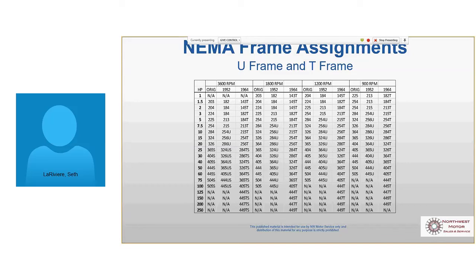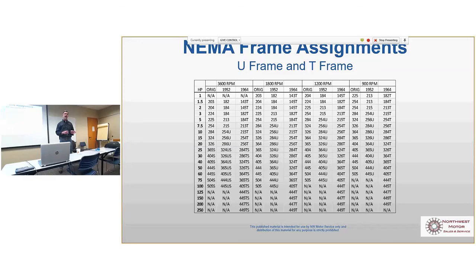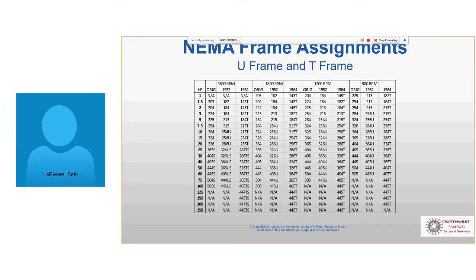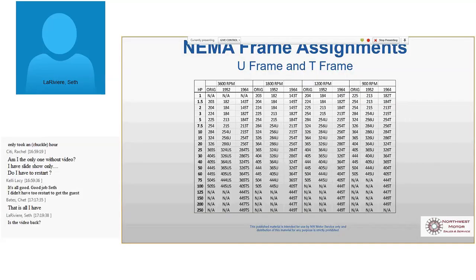So it's not that they're bad. They're just application specific. If you've got a 10 amp motor, you've got to use the 10 amp IEC contactor. There's no range like there is on the NEMA side, right? So as long as you design your system correctly and put the right motor in there and never ask it to do more than it should do, all that IEC stuff is great. Starters, contactors, motors, blah, blah, blah. But in the real world, that's just not how it is. Stuff gets overloaded and people like rugged, heavy-duty stuff.